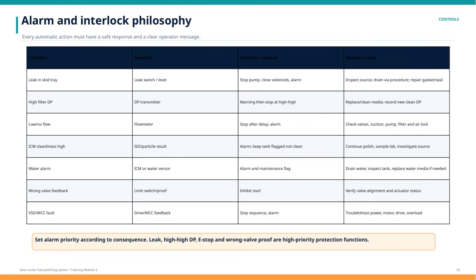This way, operators always know what's happening and what action to take if needed. Looking at the controls table, we see various conditions, how they're detected, what the controller does in response, and what the operator should do. For example, if a leak is detected via a leak switch or level sensor in the skid tray, the controller will stop the pump, close solenoid valves, and trigger an alarm. Then, the operator must inspect the source of the leak, follow the draining procedure, and repair the gasket or seal.